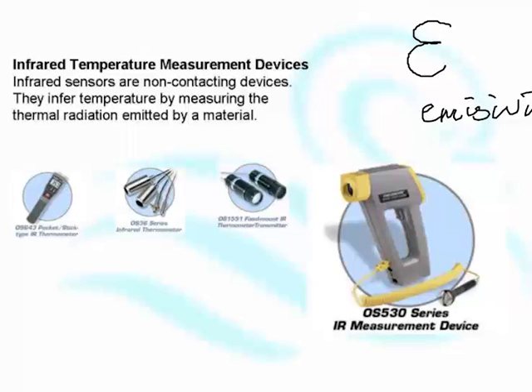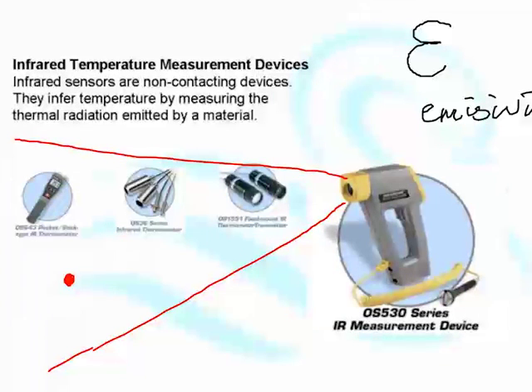Now, where people get confused, where people get mixed up, is with the fact that these things also send out a tiny little laser dot. And if they send out a tiny little laser dot, people are mistaken into thinking that where that little laser dot is touching is what they're measuring. If you're a long distance away, you're also measuring the air in between. If you're a long distance away, the actual sensor is not seeing a tiny little dot. The sensor spreads out. And if you're not measuring something that's black, your emissivity is probably not 0.9. If you're measuring something shiny, then your emissivity is wrong.